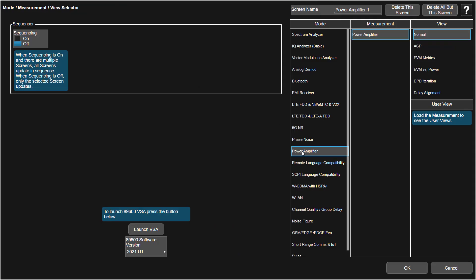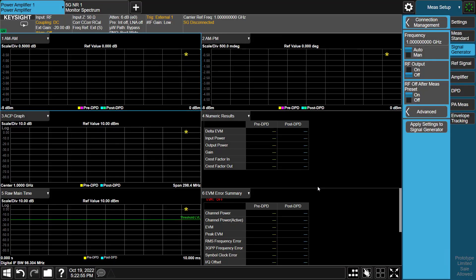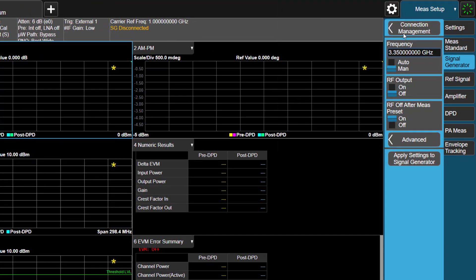In XApps, click on the main tab to open the mode measurement view selector screen. Select the Power Amplifier mode, then Power Amplifier measurement, and press OK. In the Power Amplifier measurement, go to the Signal Generator tab. Set the center frequency to 3.35 GHz. Click on Connection Management.